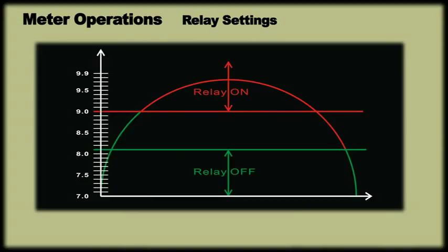Now, what is hysteresis? It is the percentage value for which the relay will not reset after getting energized. In this case, since the pH value is set at 9.00 and the hysteresis is kept at 10%, then the high relay will get energized the moment pH exceeds 9.00 and will remain energized until the pH value falls to 8.1.